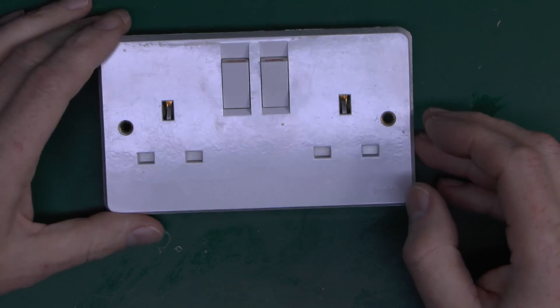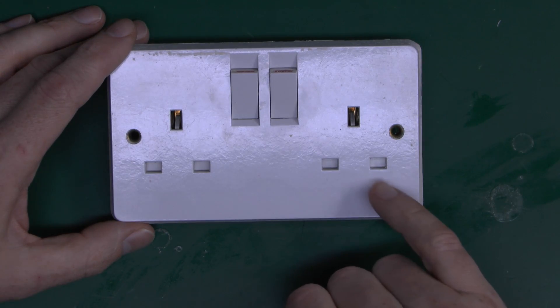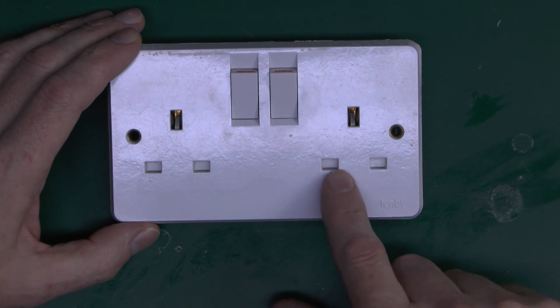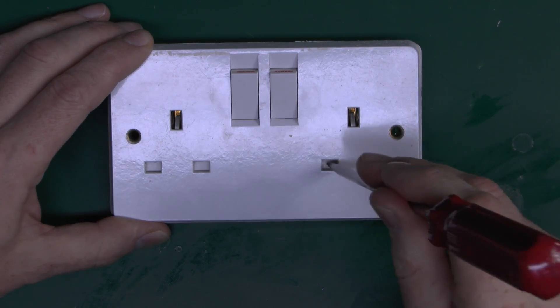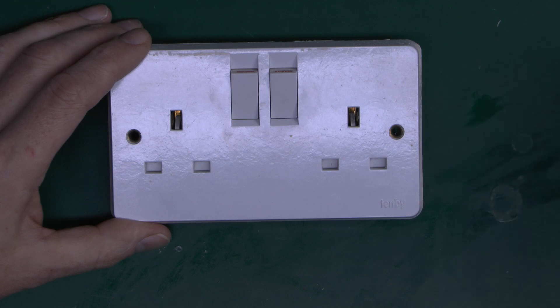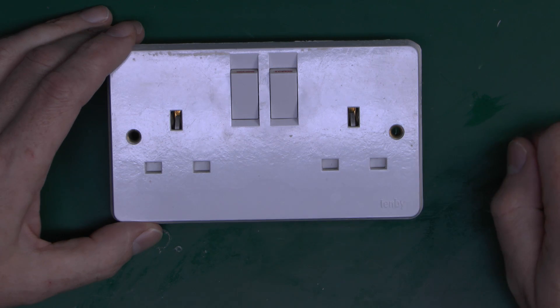Now what I have here is a standard UK socket outlet, and this is a double. It also happens to be broken, which is the subject of another video. But the point about this is that you can see inside the line and neutral holes here, and there's actually a shutter inside, so you can just see it's a block of white plastic. So if you were to take some implement and try and shove that in there, then you'll see it doesn't actually get anywhere — you can't make contact with any live parts. And every UK socket outlet that's been installed since the 1940s has this as a built-in feature, as this is actually required by the standard.